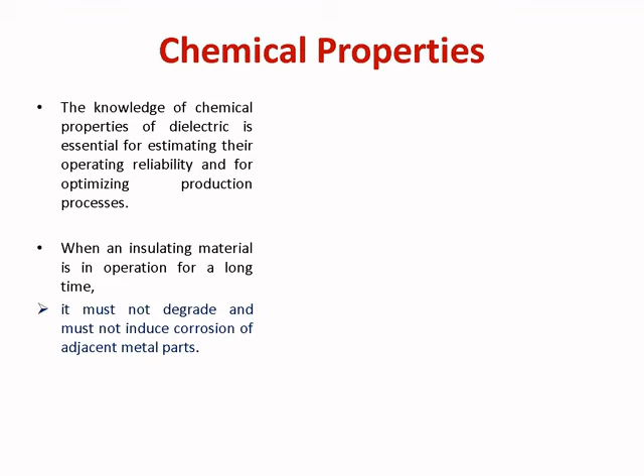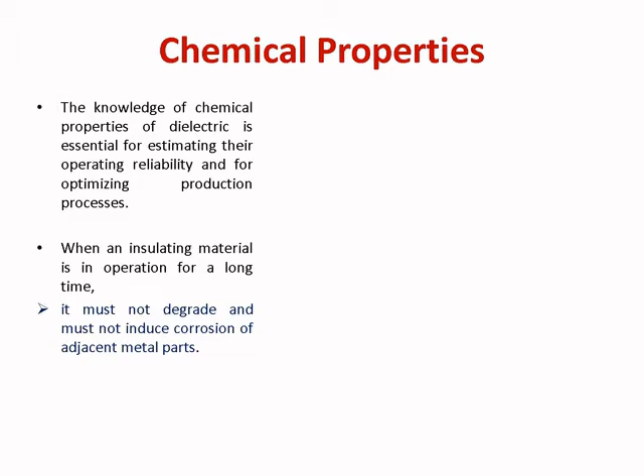When an insulating material is exposed to the environment, that is, if it is designed for outdoor applications, in the normal span of operation of the insulator, it must not degrade and must not induce corrosion of adjacent metal parts. It also must not react with the various environmental substances such as water, gases, acids, alkalis, salt solution, etc.